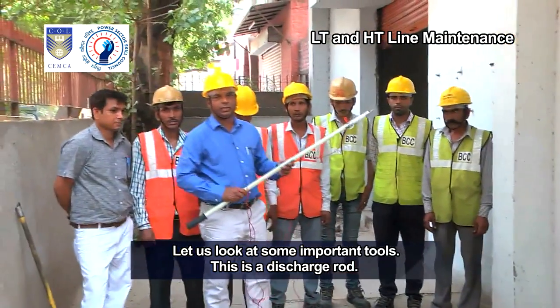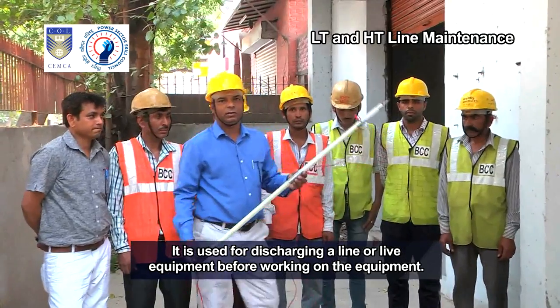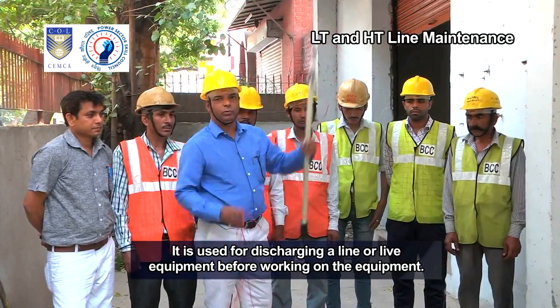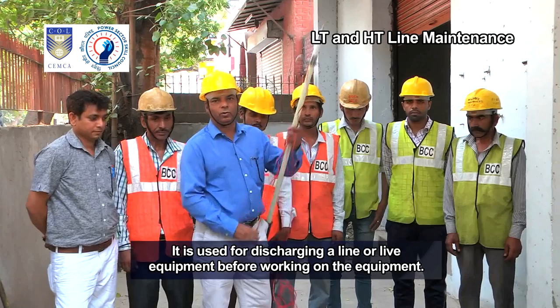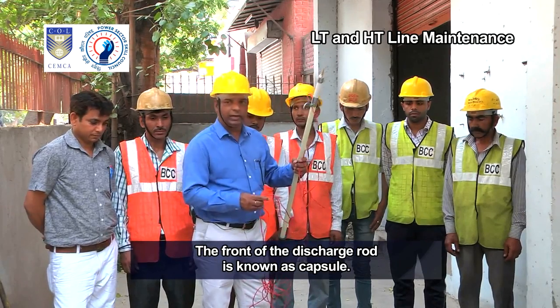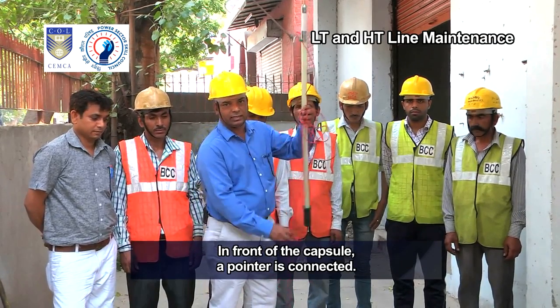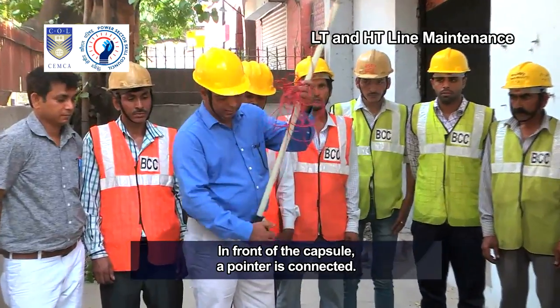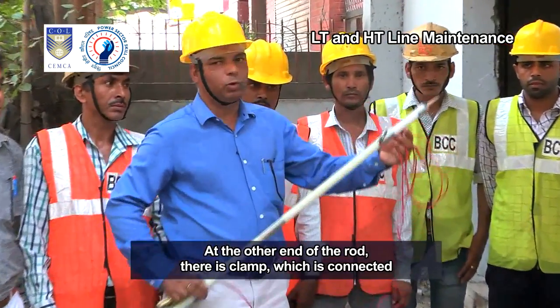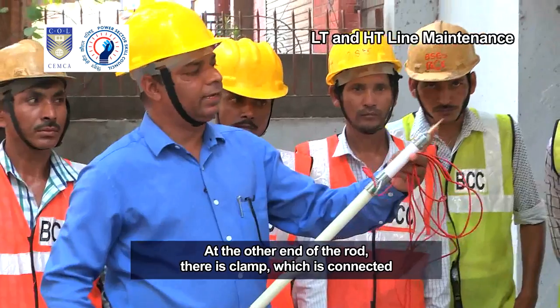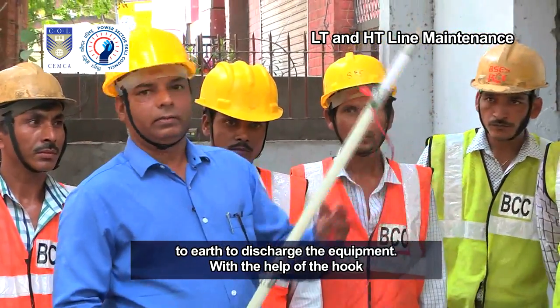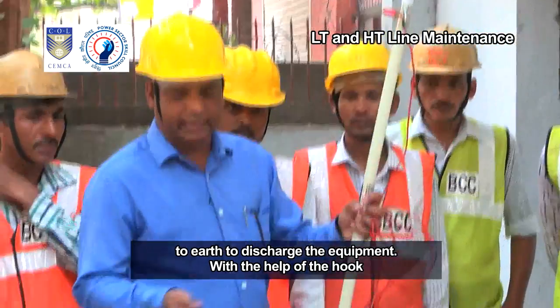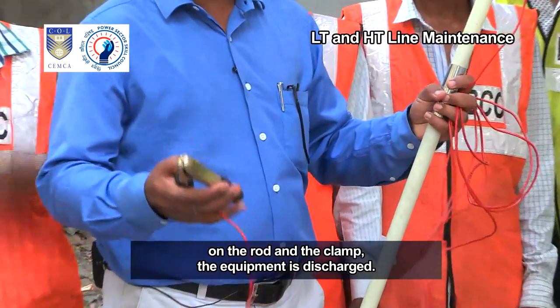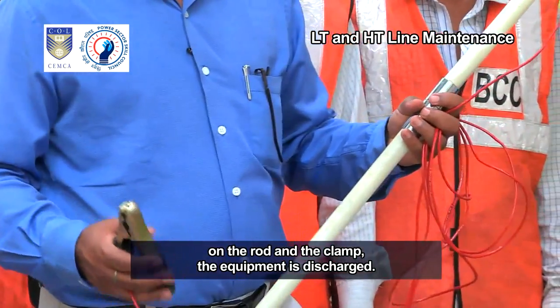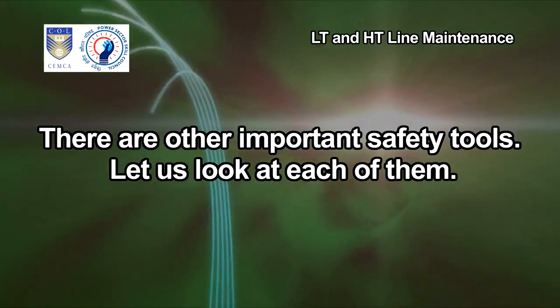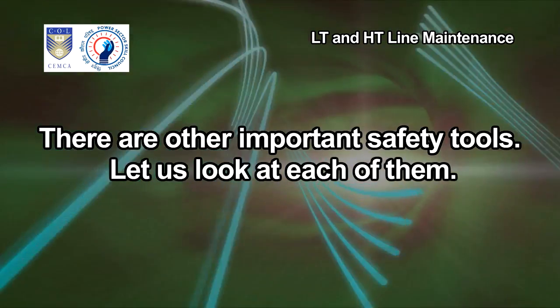This is a discharge rod. It is used for discharging a line or live equipment before working on the equipment. The front of the discharge rod is known as capsule. In front of the capsule, a pointer is connected. At the other end of the rod, there is a clamp, which is connected to earth to discharge the equipment. With the help of the hook on the rod and the clamp, the equipment is discharged. There are other important safety tools. Let us look at each of them.